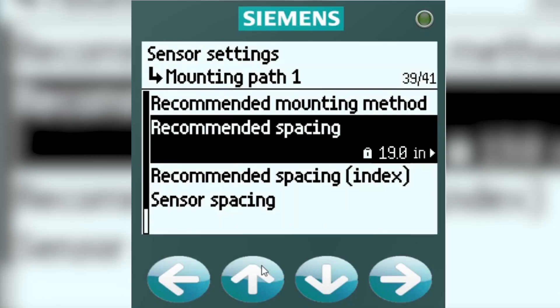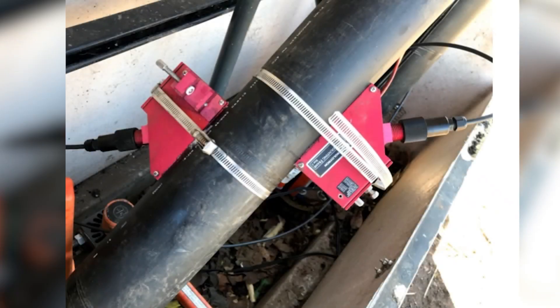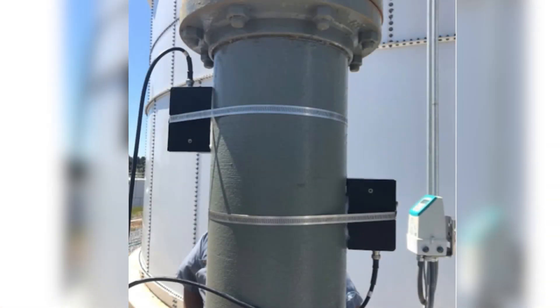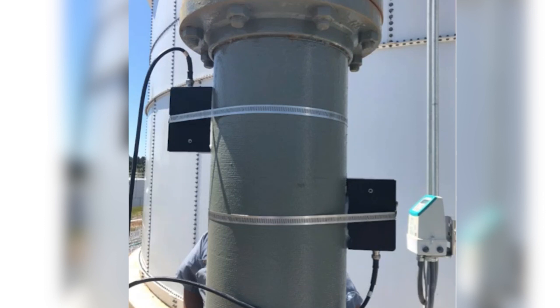Alternatively, we have Recommended Spacing in Inches. Here's an example of a vertical direct mount, and in this case, the flow is going upward. You should always avoid flow going downward on vertical pipes.